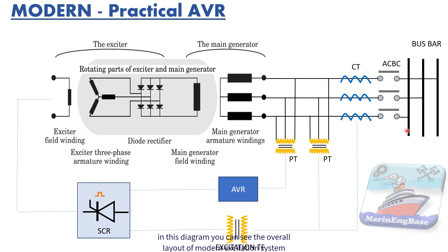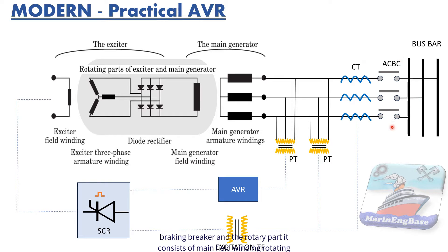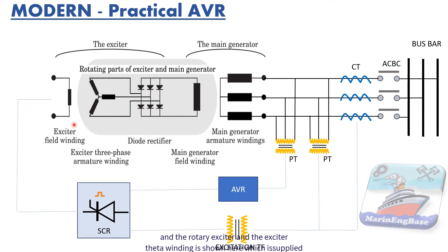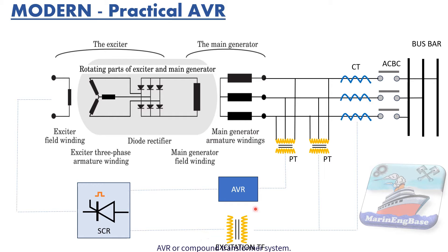Let's get started with the modern practical AVR. In this diagram, you can see the overall layout of a modern excitation system. This part shows the generator stator winding, which gives the output to the bus bar through the circuit breaker. The rotary part consists of the main field winding, rotating diode bridge, and the rotary exciter. The exciter stator winding is shown here, which is supplied through a SCR unit, excited by the AVR or compound transformer system.